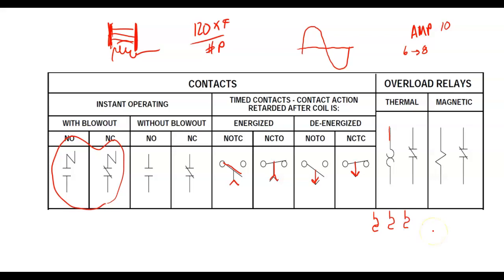those are going to have to be rated to let the motor start. In fact, they're rated between 125 to 150% over what their maximum current is. And then you round up to the next standard value. So you multiply it by 1.25, and if it doesn't fall on a standard fuse, you don't round down, you always do what? Always round up. So the problem is, if it's going to let that motor start, and the motor stalls, those fuses will just sit there and your motor will just flat burn up.